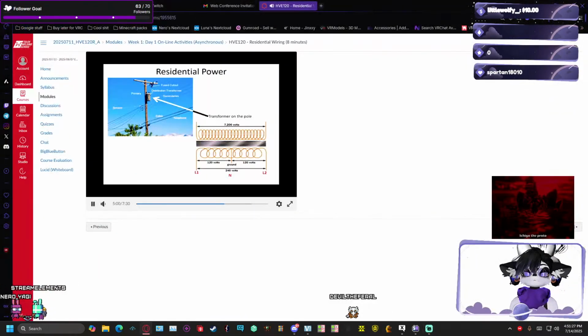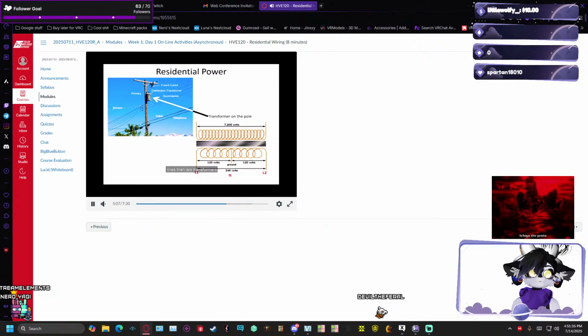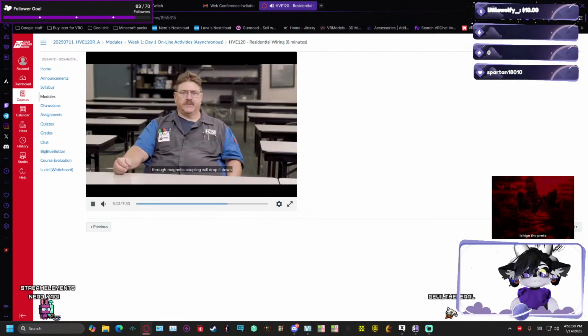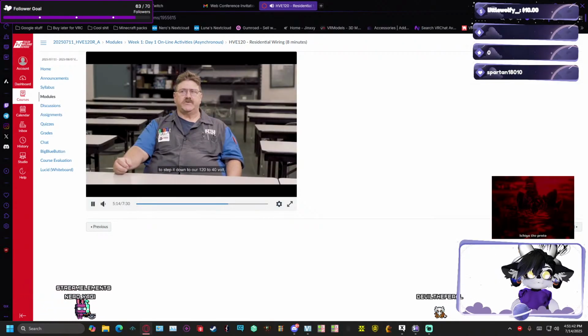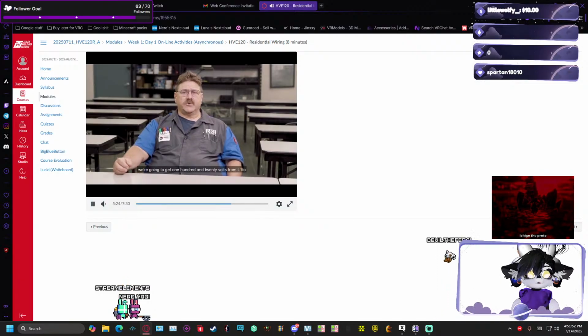It ends up going from there into our residence, and you'll see the 7200 volt transformer on the slide. That's your typical primary voltage on those lines. Then our transformers, through magnetic coupling, will step it down to our 120, 240 volt, which we then use in our residential applications. So from L1 to our neutral, we're going to get 120 volts. From L1 to L2, we're going to get 240 volts. They call this single phase power.